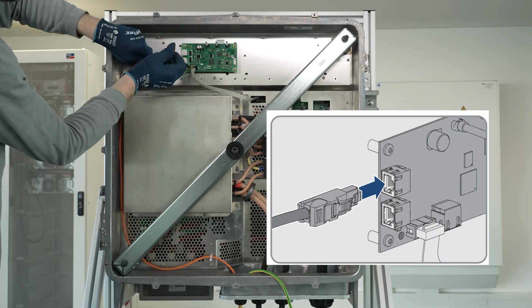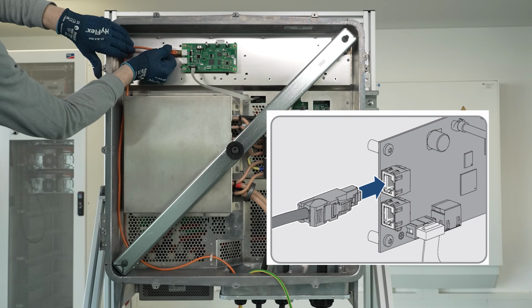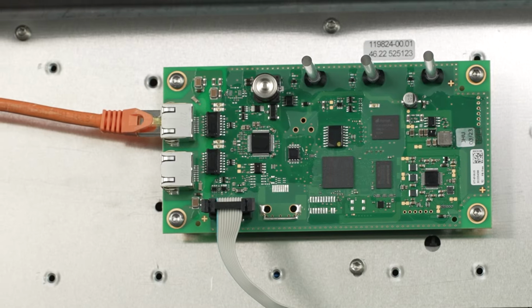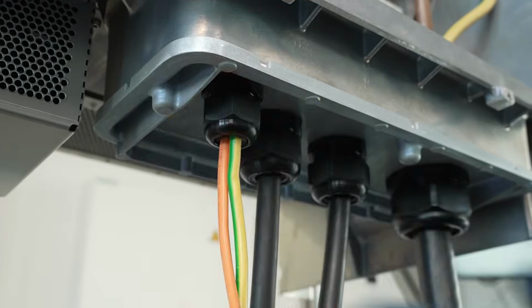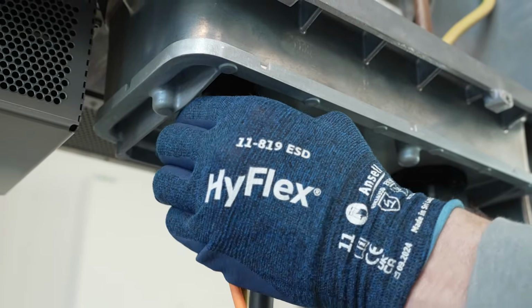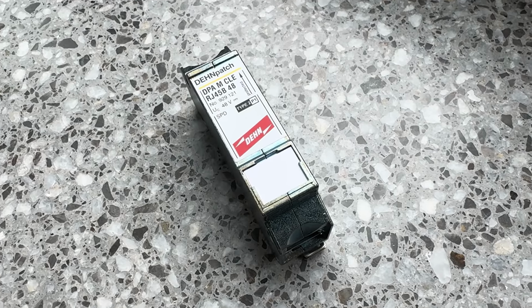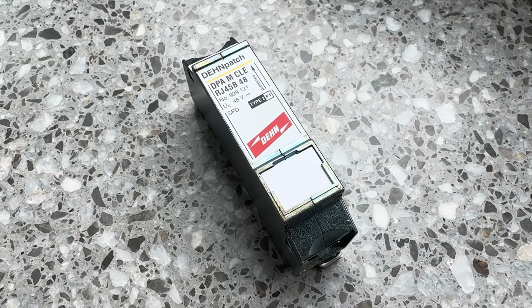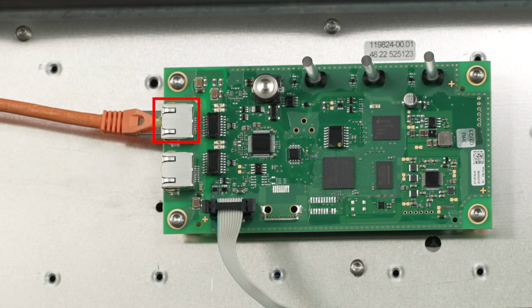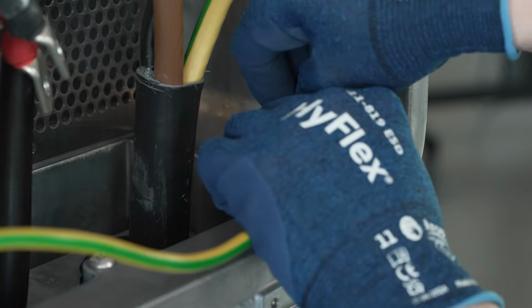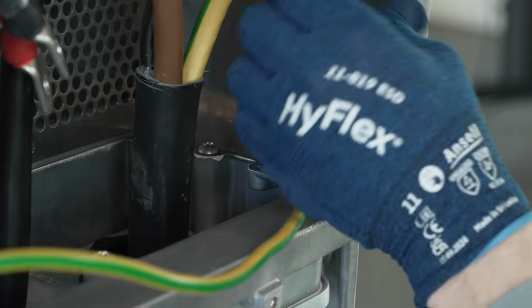Afterwards, we plug the network cables into the network sockets. By pulling evenly, we check whether the cable is securely in place. Finally, we hand tighten the lock nut. For outdoor installations, we first install a surge protector. Lastly, we either connect the network cable directly to the router or network the inverters in a line topology. The additional grounding can be connected here at the designated grounding point.